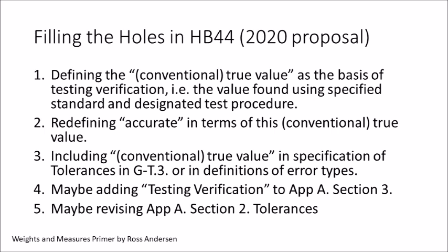Also consider adding testing verification to the fundamental considerations in Section 3 and also changing some of the parts of Section 2 where it gives the idea that maintenance tolerance is there for instrument drift, whereas what I showed is that influences are the main reason that we have maintenance tolerances.